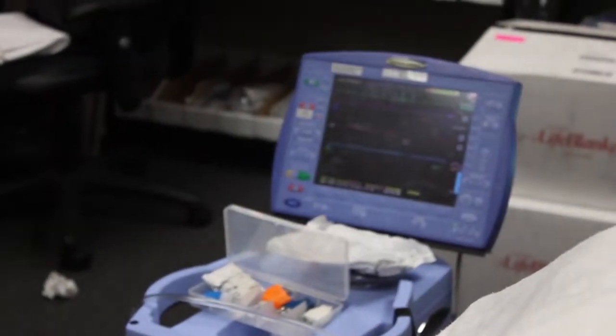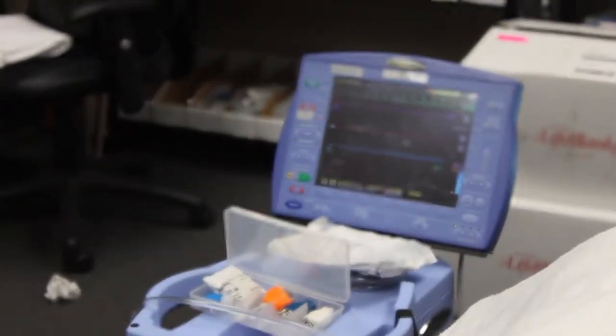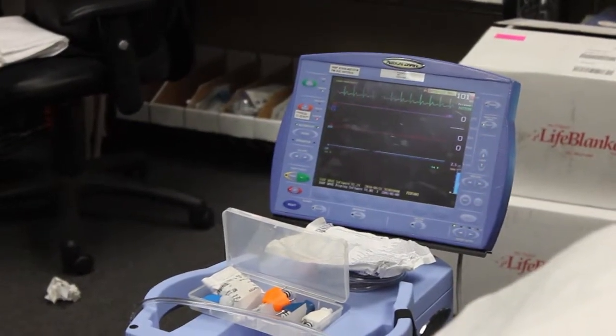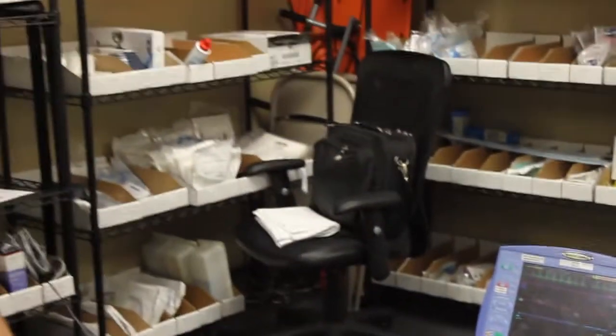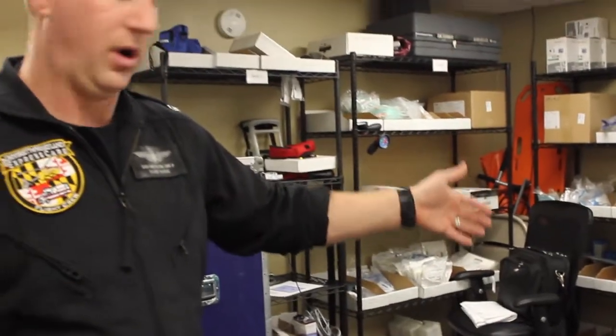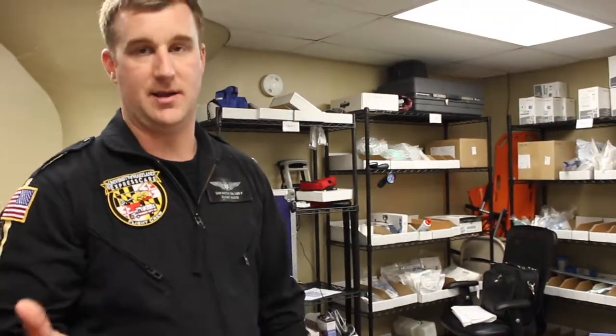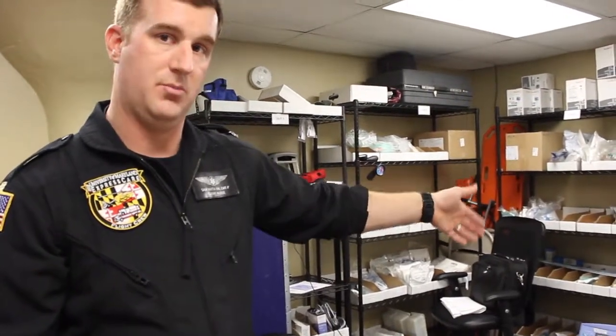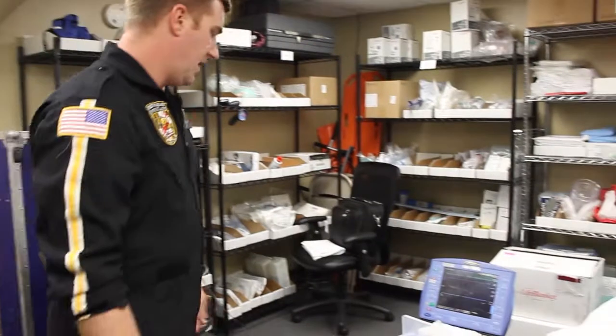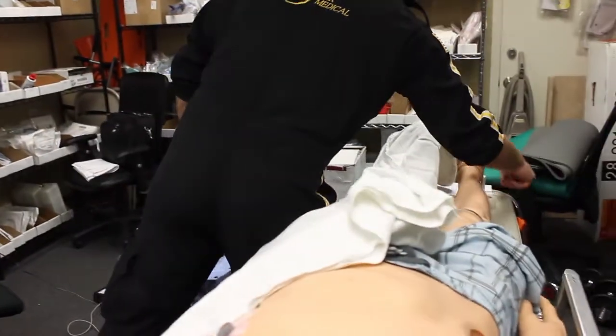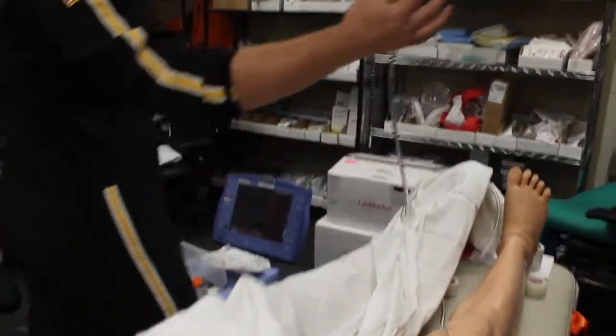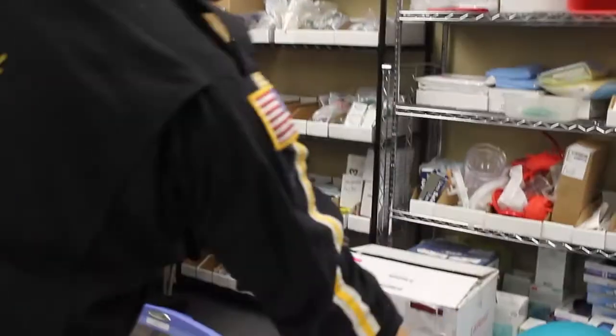So now you've got an EKG source on both pumps. We're going to go ahead and transfer at this point. Once we get a good waveform and we know we got a good secure waveform, we're going to go ahead and transfer the balloon over, because you've got a triggering source on your balloon pump.